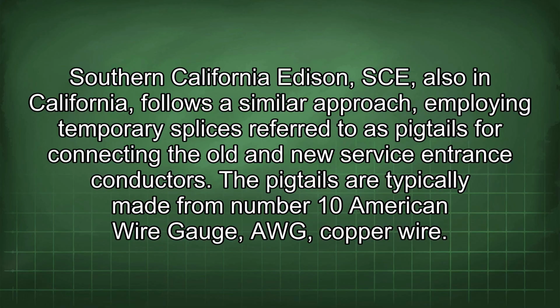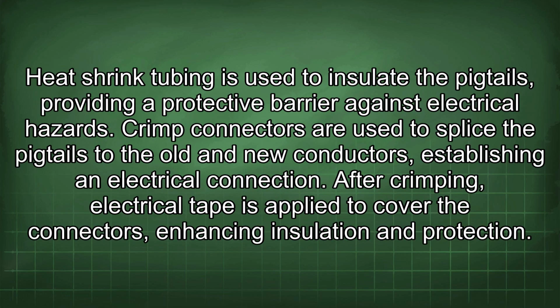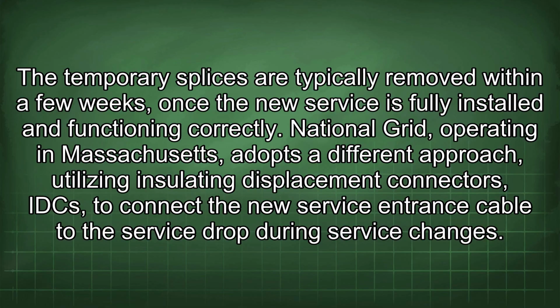The pigtails are typically made from number 10 American wire gauge (AWG) copper wire. Heat shrink tubing is used to insulate the pigtails, providing a protective barrier against electrical hazards. Crimp connectors are used to splice the pigtails to the old and new conductors, establishing an electrical connection. After crimping, electrical tape is applied to cover the connectors, enhancing insulation and protection. The temporary splices are typically removed within a few weeks, once the new service is fully installed and functioning correctly.